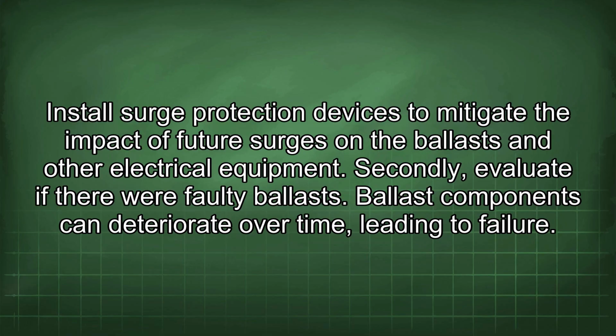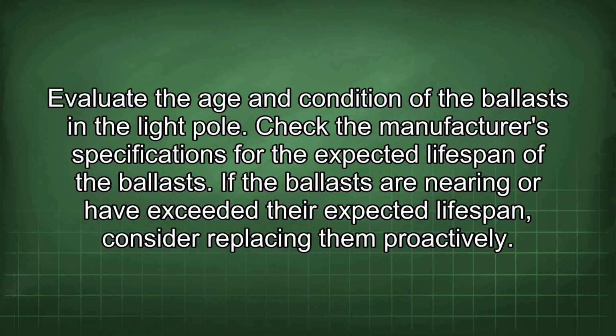Ballast components can deteriorate over time, leading to failure. Evaluate the age and condition of the ballast in the light pole. Check the manufacturer's specifications for the expected lifespan of the ballasts. If the ballasts are nearing or have exceeded their expected lifespan, consider replacing them proactively.